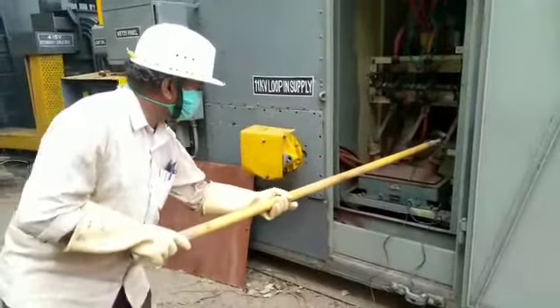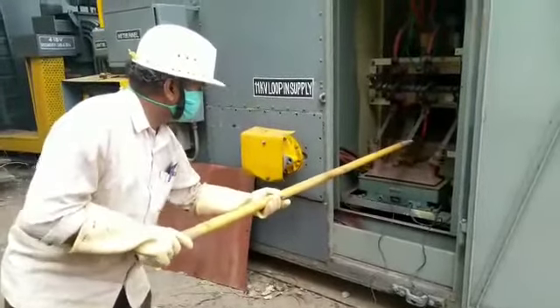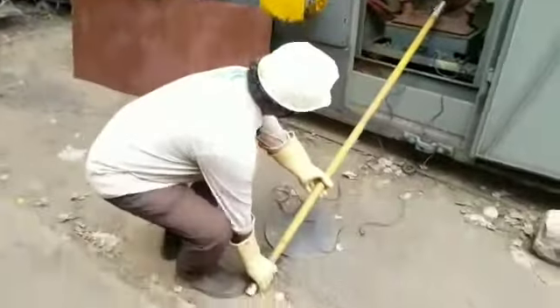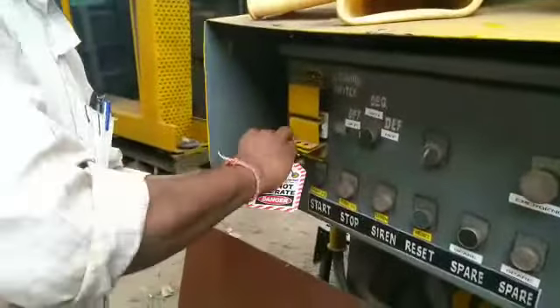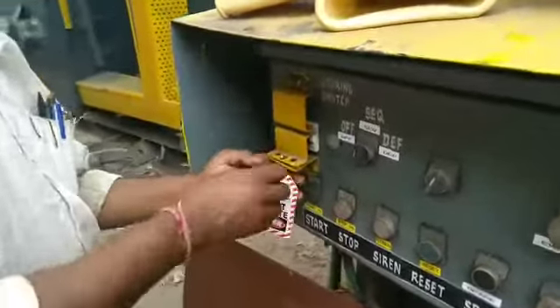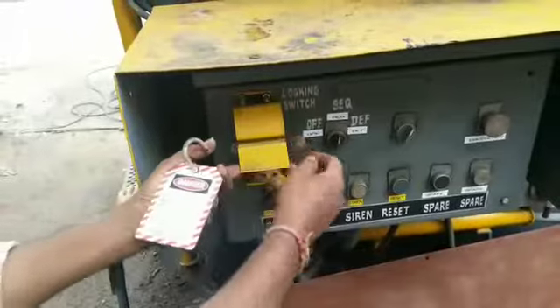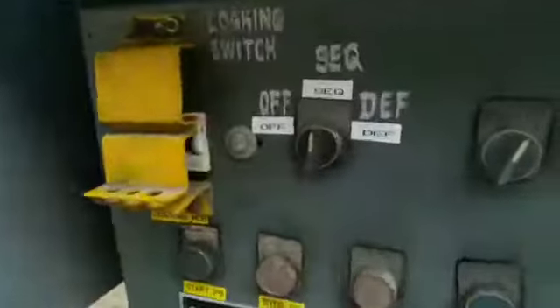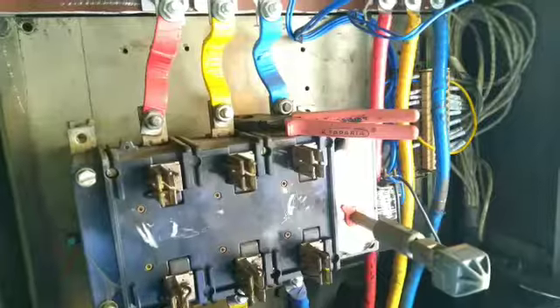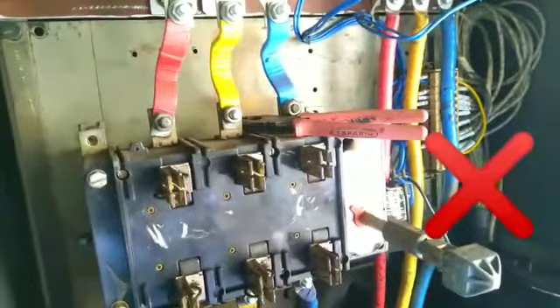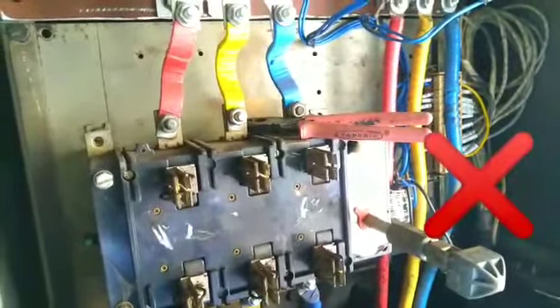First of all, discharge the residual current from all the three phases and keep the earth rod at the terminal of the isolator, and lock the MCB and put the lockout tagout. After completion of work, open the locking switch, take the earth rod and switch on the breaker. Don't keep any tools on the bus or any other electrical equipment.